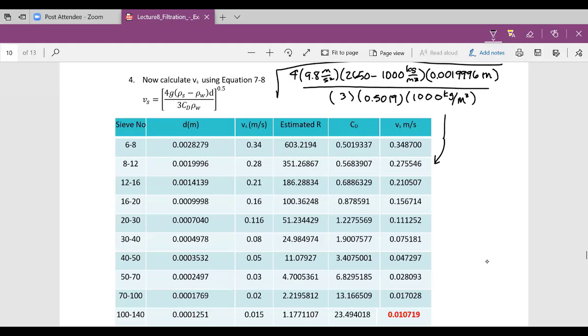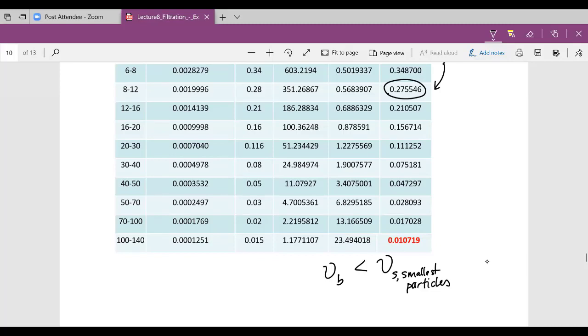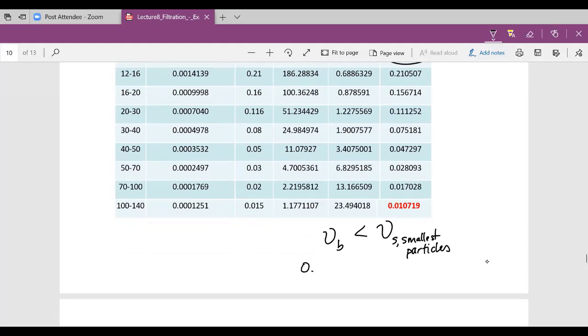We calculate the terminal settling velocity as the square root of [4 × 9.8 m/s² × particle density × diameter in meters] divided by [3 × CD × water density]. Notice the calculated value is not much different from what we estimated from the graph. We need our backwash velocity to be less than the terminal settling velocity of the smallest particles, which means less than 0.0107 meters per second.